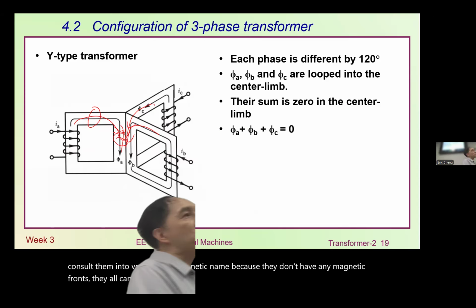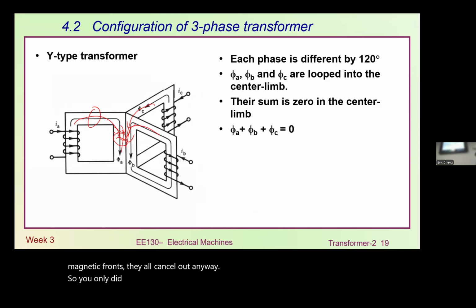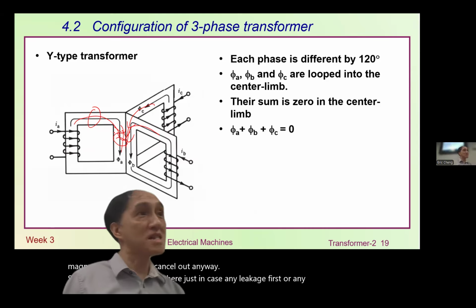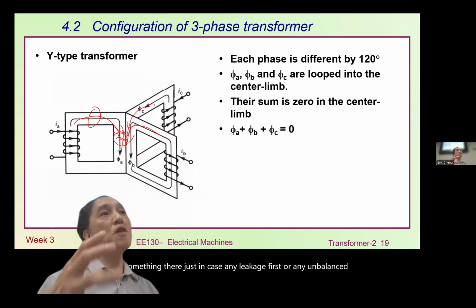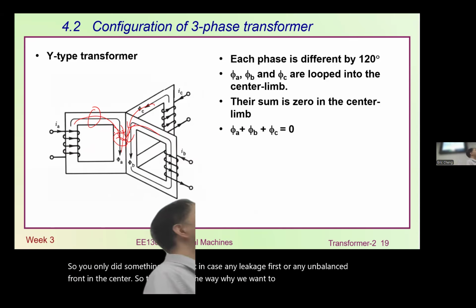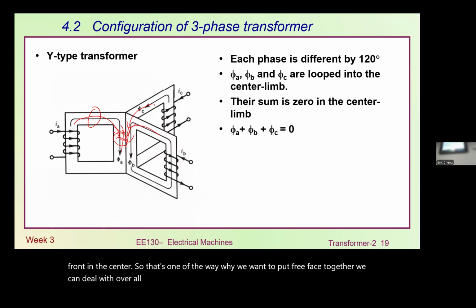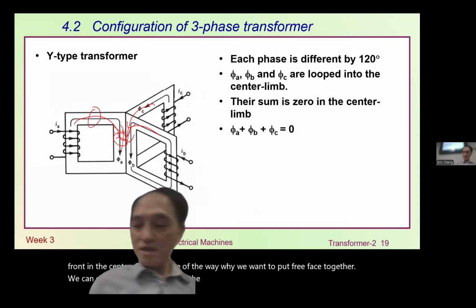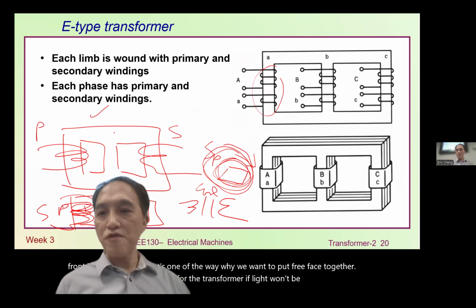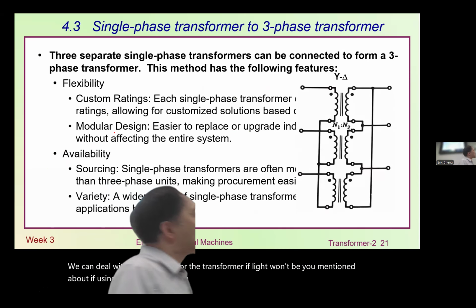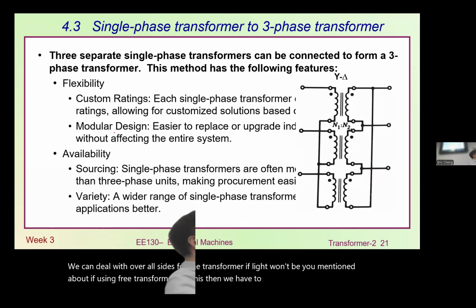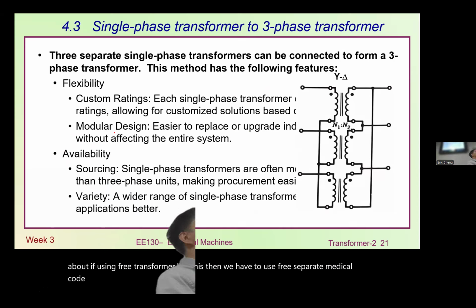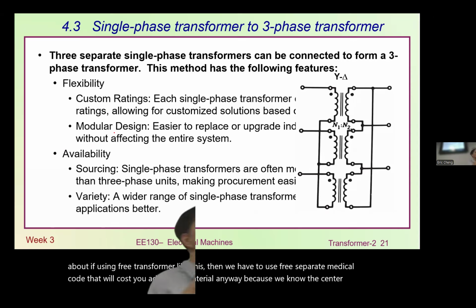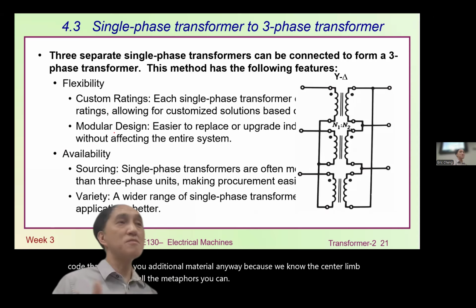So you only need something there just in case of leakage flux or unbalanced flux in the center. That's one of the reasons why we want to put 3 phases together, so we can reduce the overall size of the transformer. If we used 3 separate transformers like this, we'd need 3 separate magnetic cores, which costs additional material. But since the center limb can cancel out all the magnetic flux, we can reduce the material.